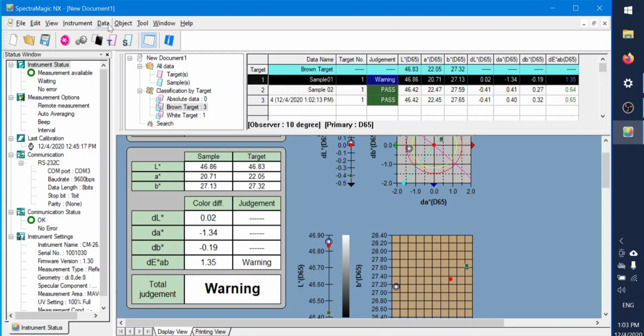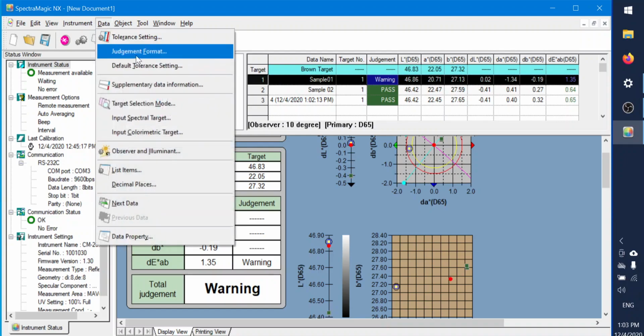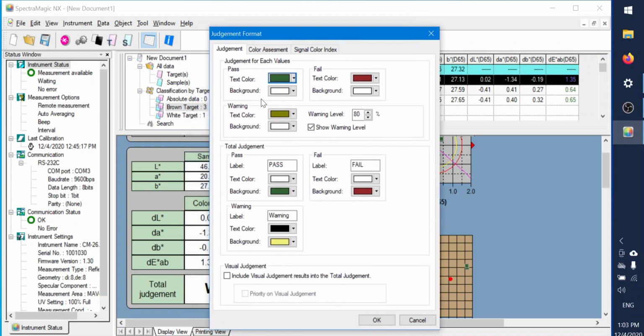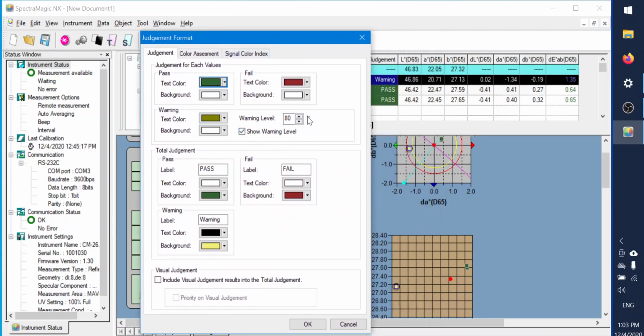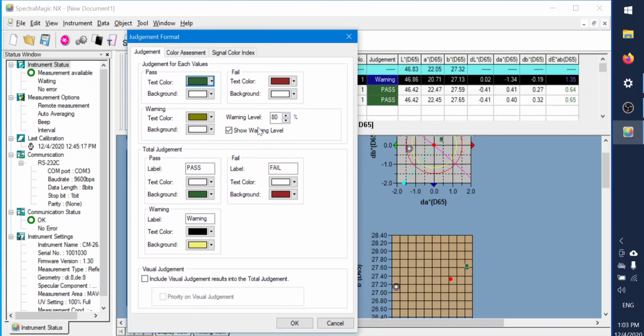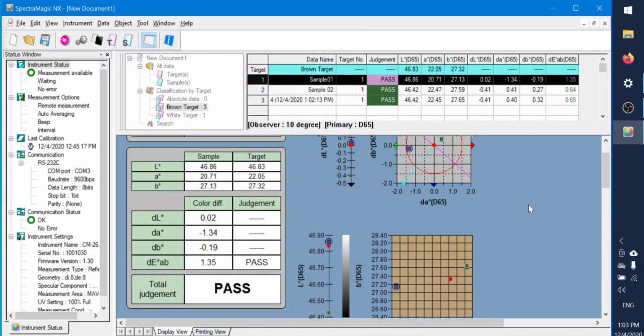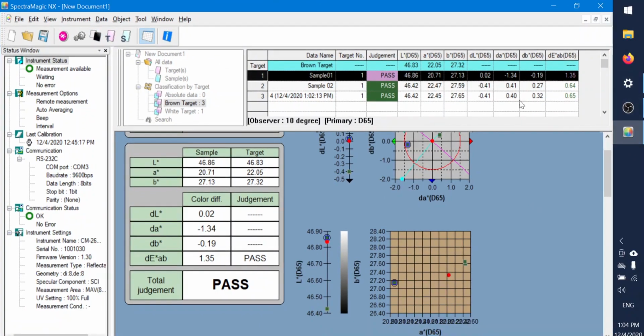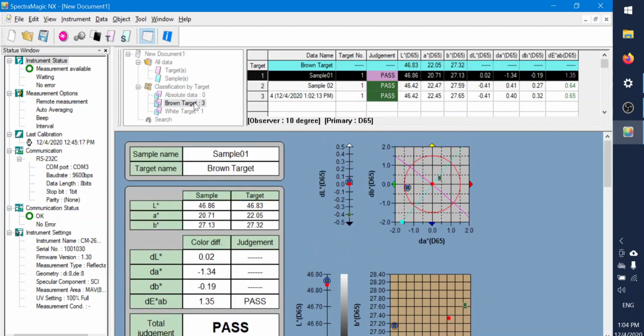This actually can be seen when you click data and you click judgment format. So it has a warning level over here. So it says warning level is 80%, the text color will change to yellow, and so this is just a good indication that the color may be coming close to failure. However, if you do not like this feature, you can just turn off this show warning level, click OK. Now everything shows pass and there is no warning indicator on this. So this will be a very brief explanation of how to use the SpectraMagic software.